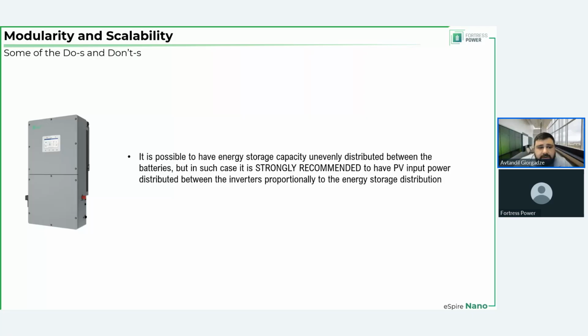So one of the ways we ask our customers to mitigate that is to have PV distribution be proportional to the storage distribution between the batteries, right? So we have 60 kilowatt hour and 80 kilowatt hour in our case. Well, how would you distribute the PV between these? If we take 80 kilowatt hour as 100%, 60 kilowatt hour then becomes three quarters, or 75%. So you would have a 75% ratio in the PV distribution as well, so that all of them receive PV power proportionally to their storage size.